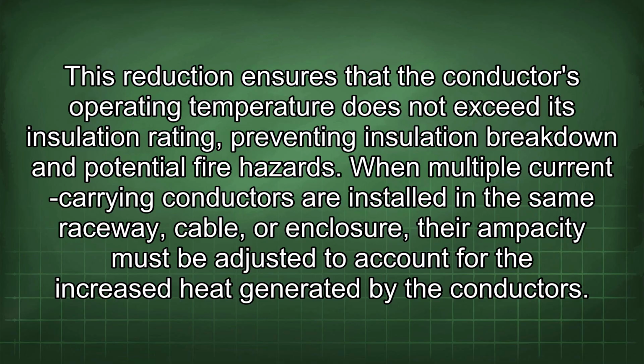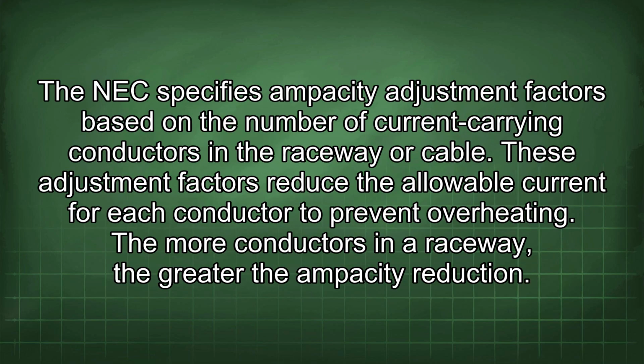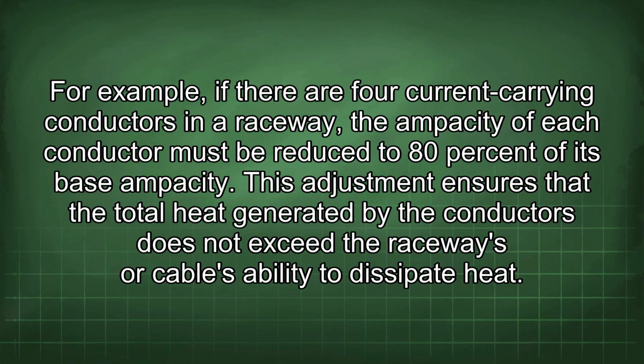When multiple current-carrying conductors are installed in the same raceway, cable, or enclosure, their ampacity must be adjusted to account for the increased heat generated by the conductors. The NEC specifies ampacity adjustment factors based on the number of current-carrying conductors in the raceway or cable. These adjustment factors reduce the allowable current for each conductor to prevent overheating. The more conductors in a raceway, the greater the ampacity reduction. For example, if there are 4 current-carrying conductors in a raceway, the ampacity of each conductor must be reduced to 80% of its base ampacity. This adjustment ensures that the total heat generated by the conductors does not exceed the raceway's or cable's ability to dissipate heat.